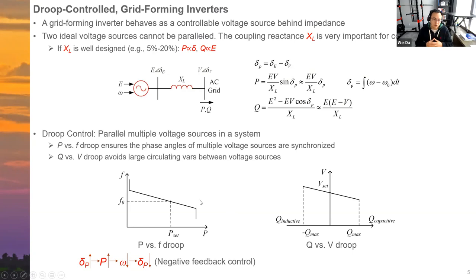So why do we need the droop control? The droop control is just to make sure multiple grid forming inverters can work in parallel in a stable manner. For example, this power versus frequency droop control is actually a very simple negative feedback control. Let's take a look at a single grid forming inverter infinite bus system. Based on this classic equation, P is approximately linear with the phase angle delta. Let's assume a small disturbance causes this phase angle delta to increase. Based on this equation, the increase of delta results in the increase of active power P. And with droop control, when P increases, the controller reduces the angular frequency omega.